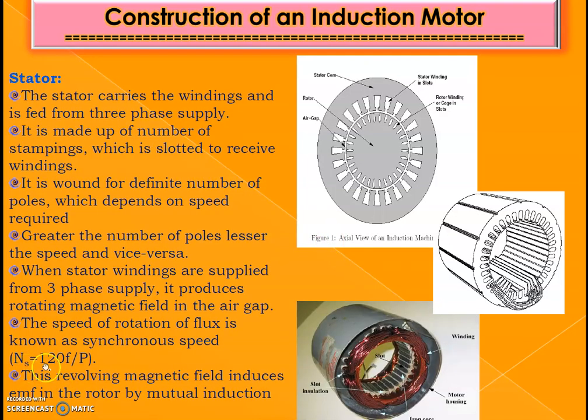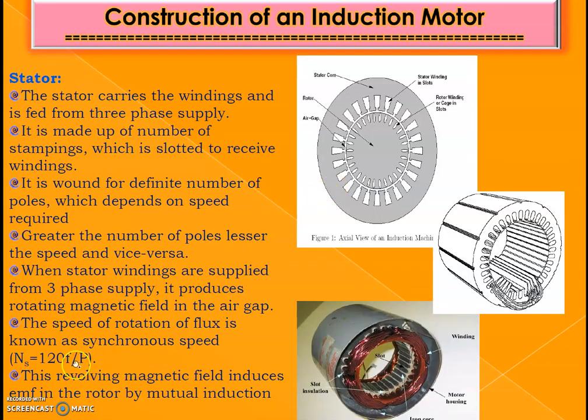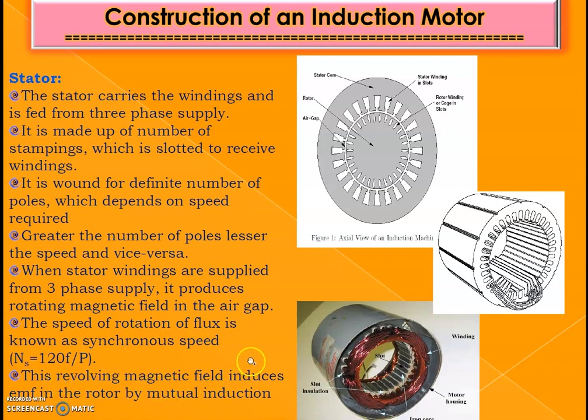The speed of the rotating flux is given by Ns = 120f / P, where f is the supply frequency and P is the number of poles. For example, if f = 50 Hz and P = 2, then Ns = 120 × 50 / 2 = 3000 RPM. If P = 4, then Ns = 120 × 50 / 4 = 1500 RPM. So as the number of poles increases, synchronous speed decreases. Keep in mind that poles always come in pairs, and this creates a revolving magnetic field that interacts with the rotor through mutual induction.